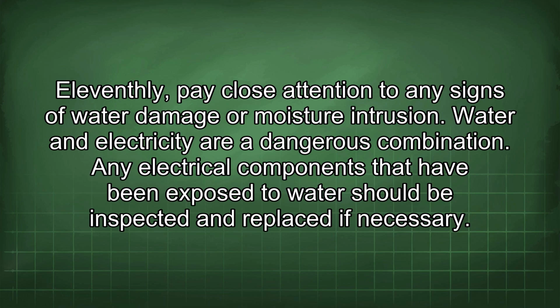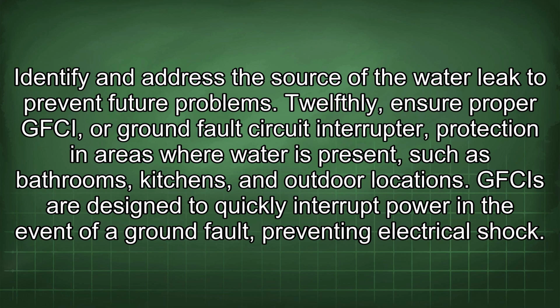Eleventhly, pay close attention to any signs of water damage or moisture intrusion. Water and electricity are a dangerous combination. Any electrical components that have been exposed to water should be inspected and replaced if necessary. Identify and address the source of the water leak to prevent future problems. Twelfthly, ensure proper GFCI, or ground fault circuit interrupter, protection in areas where water is present, such as bathrooms, kitchens, and outdoor locations. GFCIs are designed to quickly interrupt power in the event of a ground fault, preventing electrical shock.